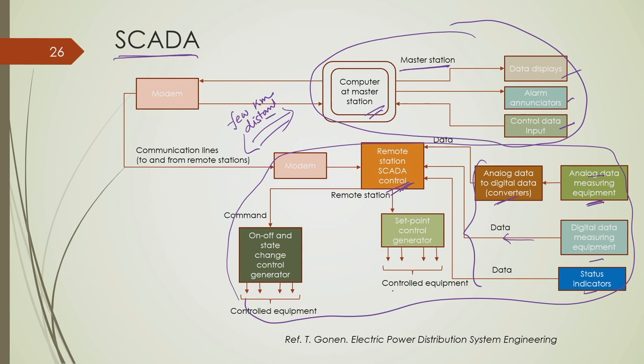The remote station also has control action generators that produce desired set points for controllable equipment, and on/off state changer controls — for example, capacitor control to switch a capacitor bank on or off. Operating the remote station from the master station a few kilometres away is the SCADA process, and a communication link with modems enables proper communication between the master station and all remotely controlled stations.